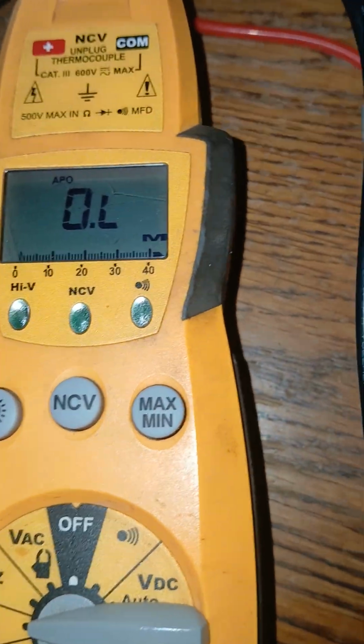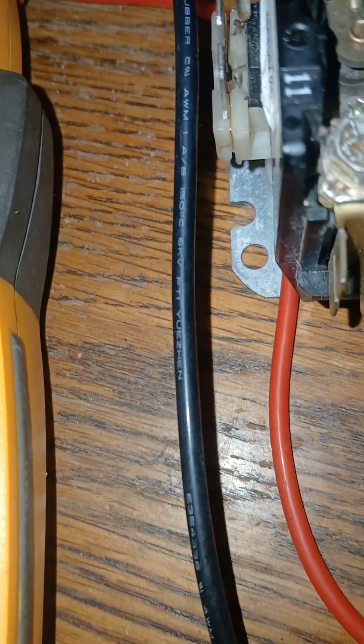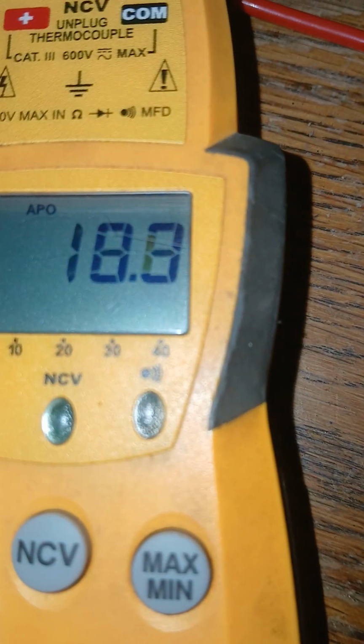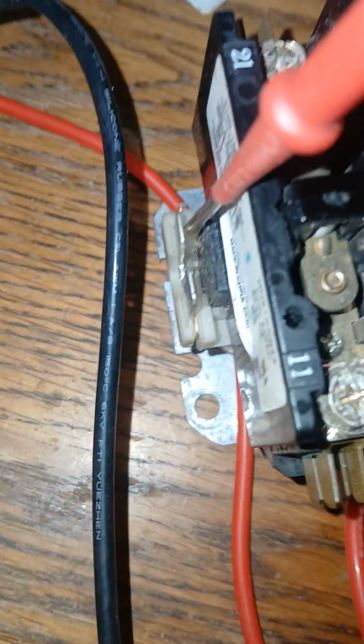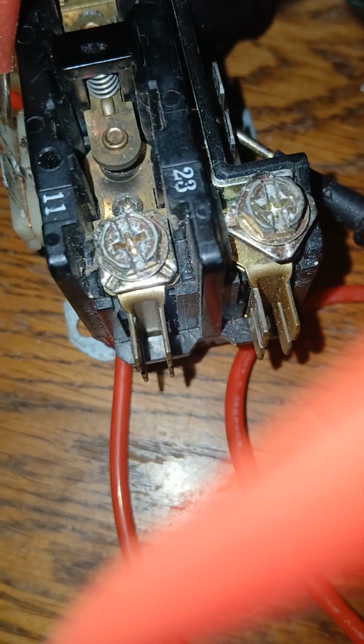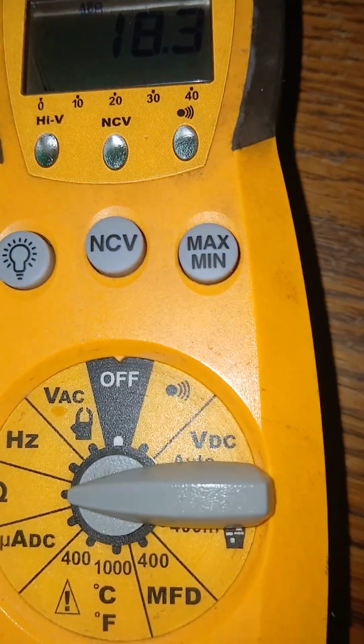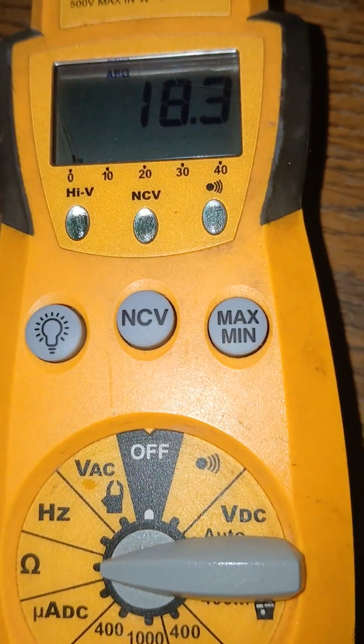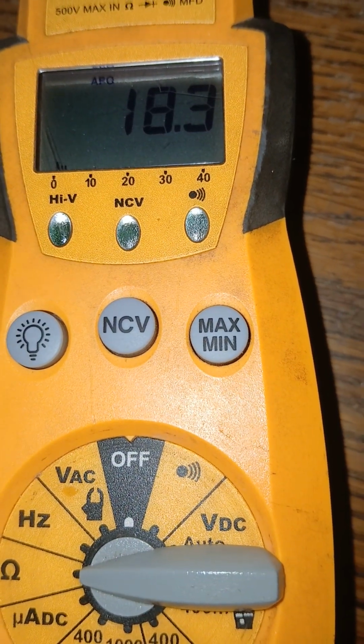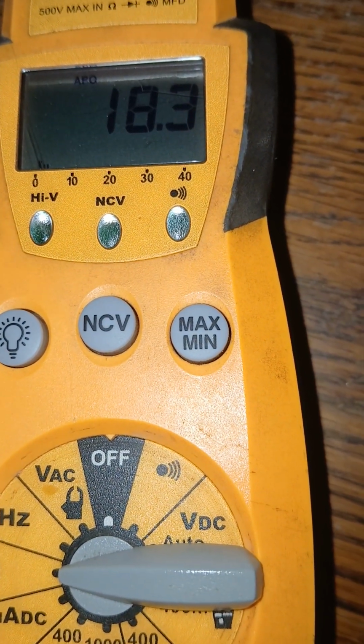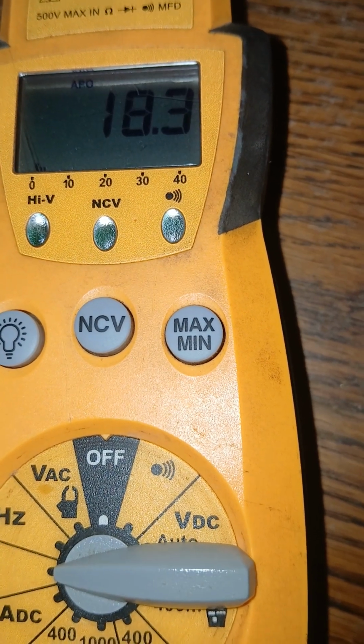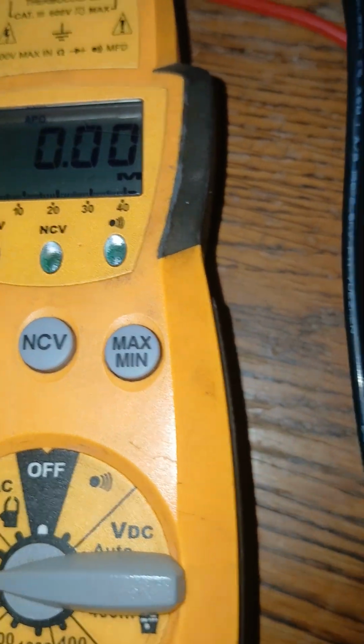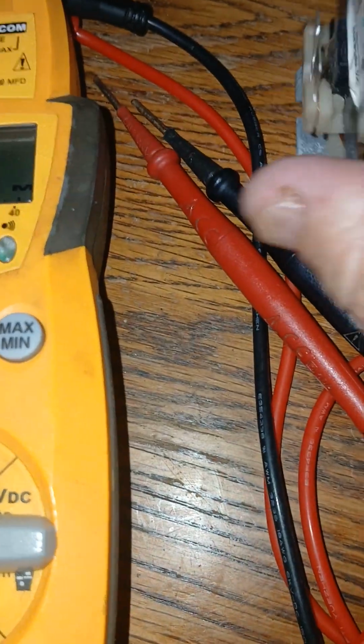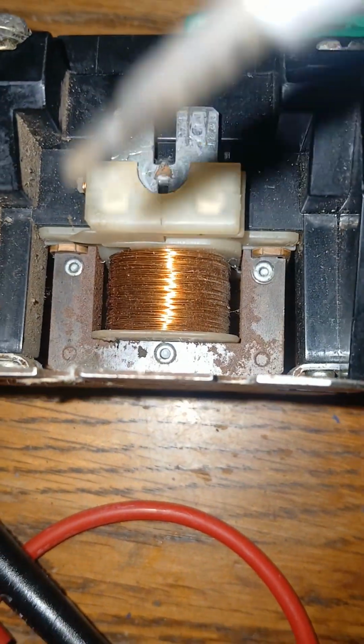But see, we're reading OL now, but if we go over here and hypothetically touch this, now we're touching both sides. We have the lead on one side, the lead on the other side, the meter set to ohms. Once the meter's set to ohms, we're reading 18.3, which indicates that this particular coil may be good. So now if we pull the leads away and we take the contactor and flip it up on its side, then we can actually see the coil.